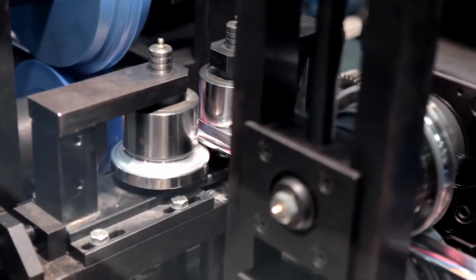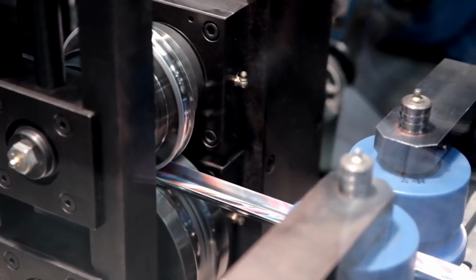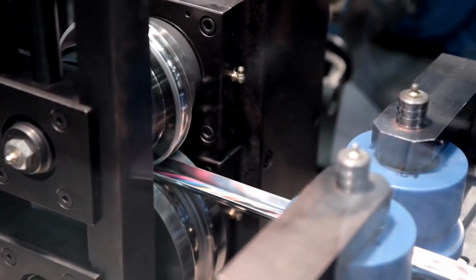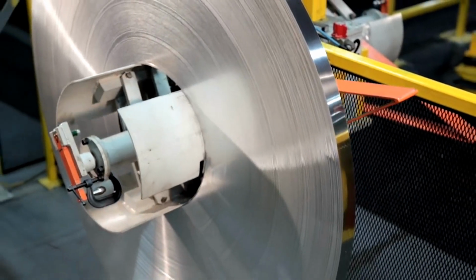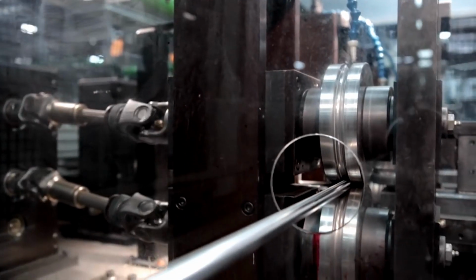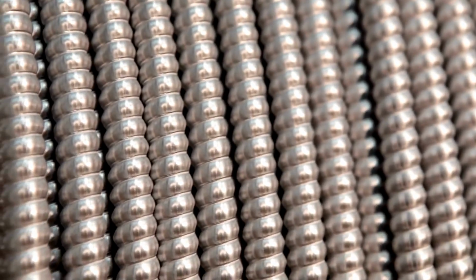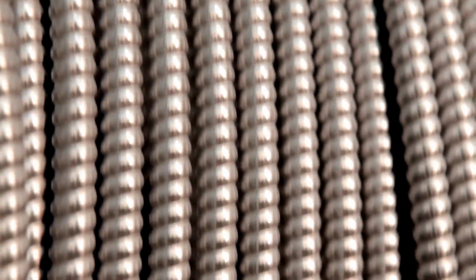CCW, or continuous corrugated welded cables, are specially designed and manufactured to operate in extremely hazardous locations. This product employs an aluminum metal tape which is formed, welded, and corrugated around the cable core for extra strength, making the cable impervious to gas, liquids, and vapors before the outer jacket is applied.